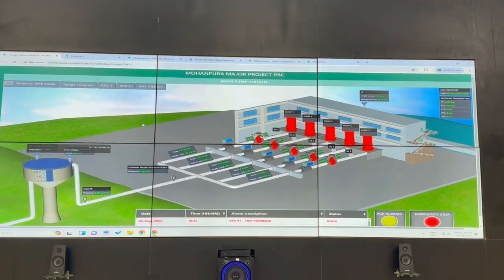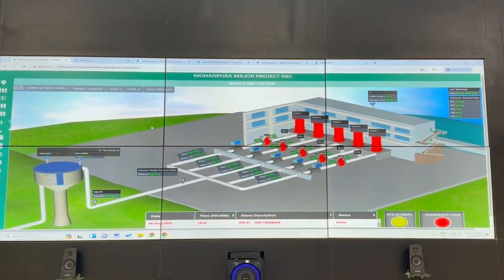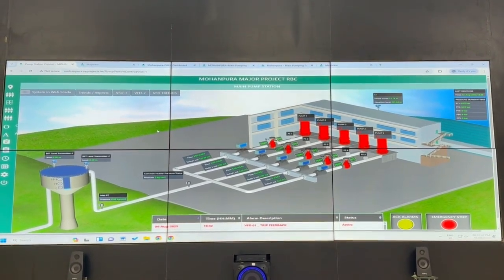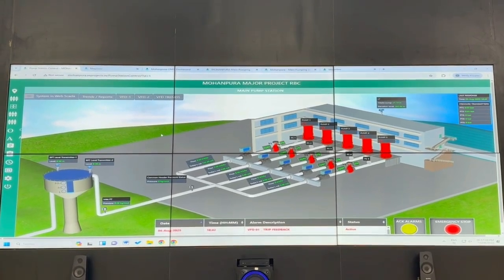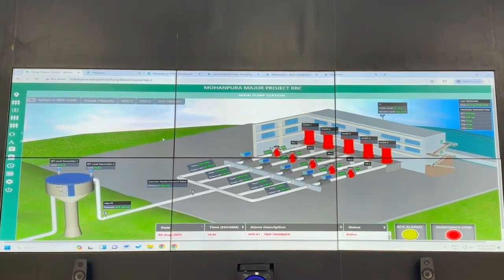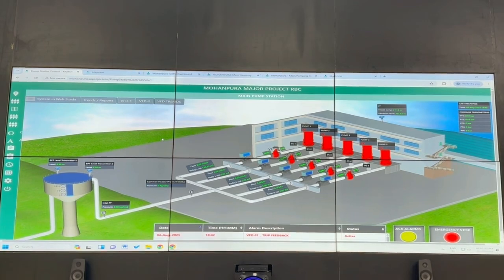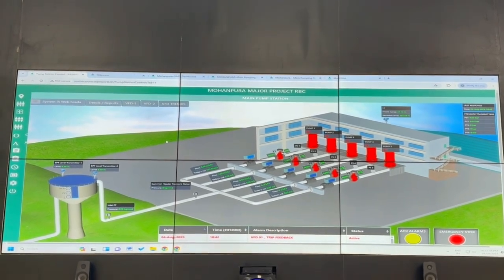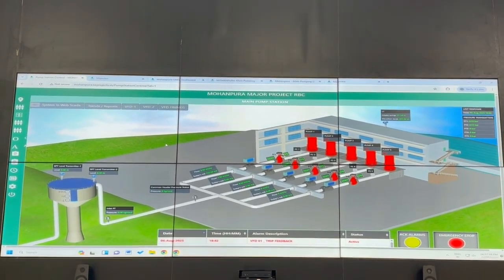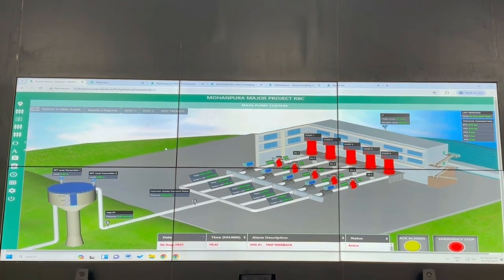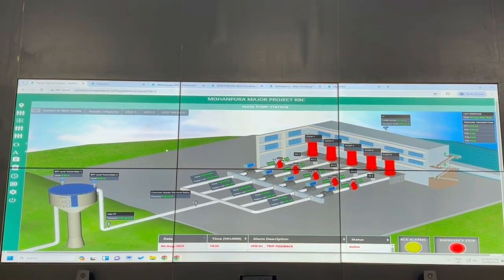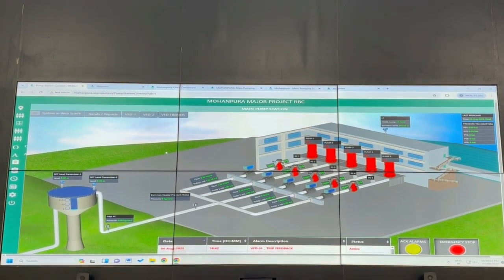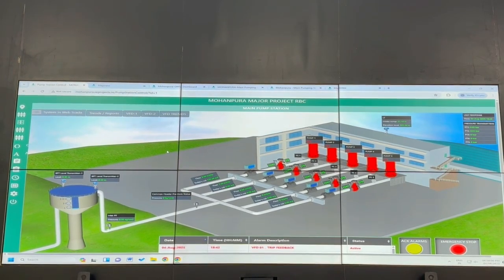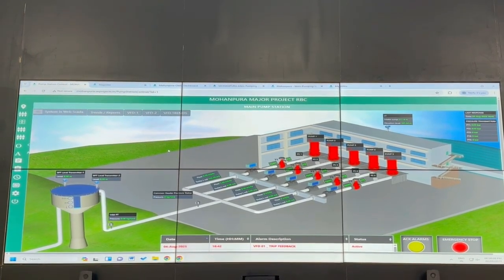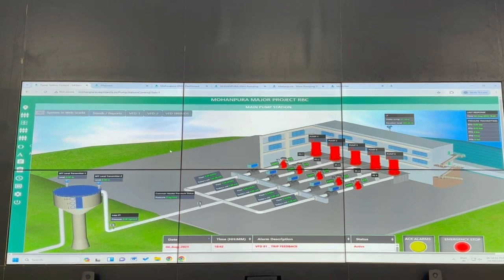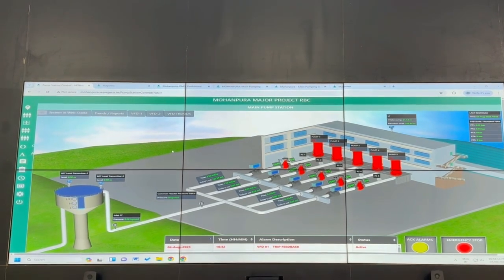This is the SCADA system. We are in the command center right now. The SCADA is divided in two parts: the pump house SCADA and the field SCADA. This is the sump area where we are sitting here, the pump house area, and this is the pump house SCADA we are seeing right now. It has transmitters in place that are showing the sump level, pressure gauge is in place, pressure switch is there, flow meters, color coding for the sump is also done.